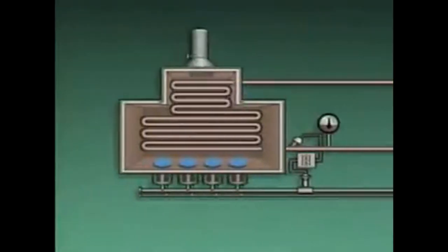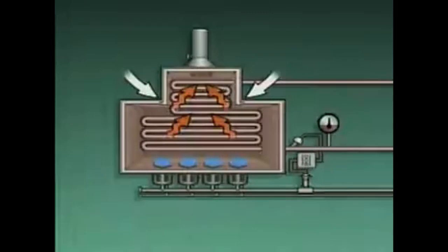One fairly common problem is an air leak. If air leaks into a furnace, it can lower the temperature of the flue gases inside. An air leak can also lower the temperature of the tubes and the outlet temperature of the process fluid. If this happens, the temperature controller will call for more fuel to bring the outlet temperature back where it should be. Since more fuel is needed, the cost of operating the furnace goes up.